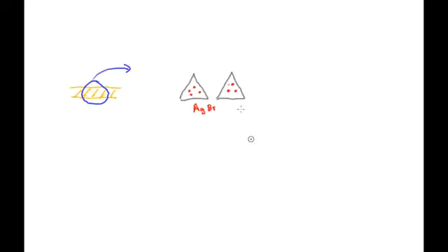For radiotherapy applications, we actually have two types of film: radiographic film and radiochromic film. They're different, and I'm going to go through them separately. I'm going to start with radiographic film because it's similar to what you might know, the traditional old photographic film. All of these films have an active layer that's several microns thick. If I zoom in to that layer, what I would see are these little crystals in radiographic film, and these have inside them silver crystals. Typically it's silver bromide or silver iodide.